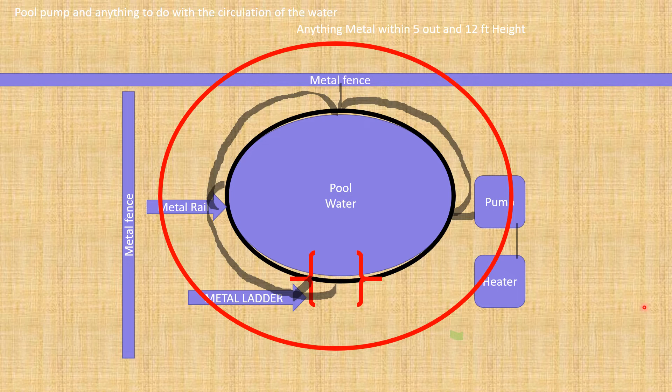If that were not the case, then you're going to install a water bond fitting right here, somewhere in this circuitry system. You're going to set it where it's always in contact with the water so it won't be affected by the backwash. And you're going to install a pool bond fitting there.